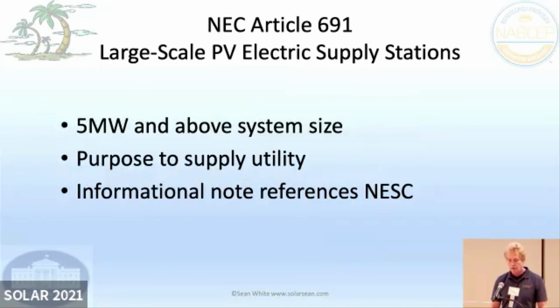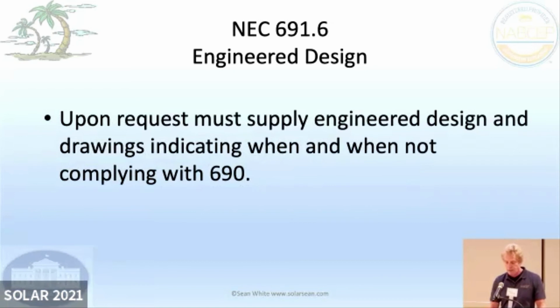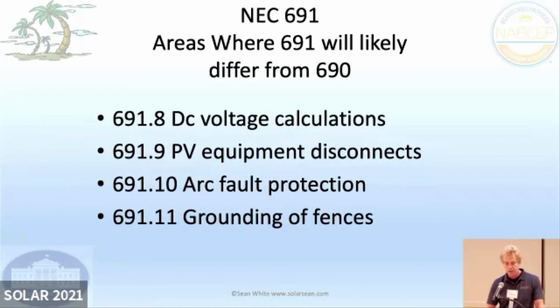So that's for 5 megawatts and larger, and it's never going to supply loads. It only supplies the utility. It's not like you're going to power your Amazon warehouse with this. You're powering the utility. And there's a lot of references to the National Electrical Safety Code. Things will be done under engineered design. And these are some of the things that will often differ from Article 690.